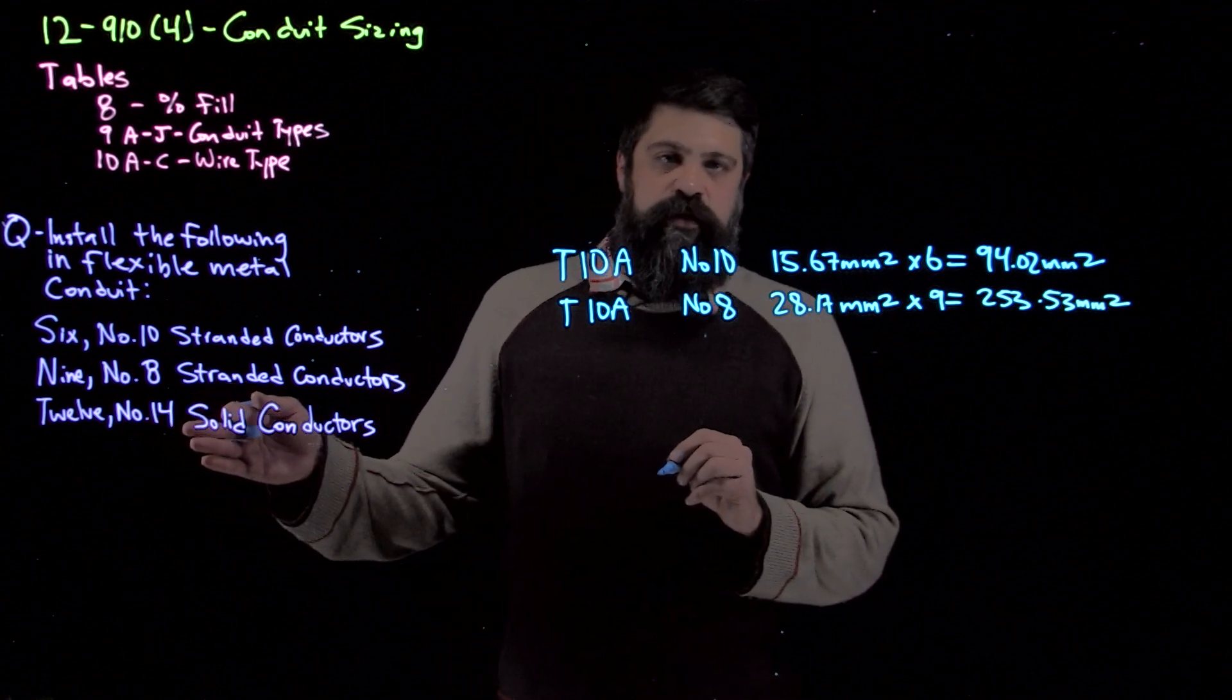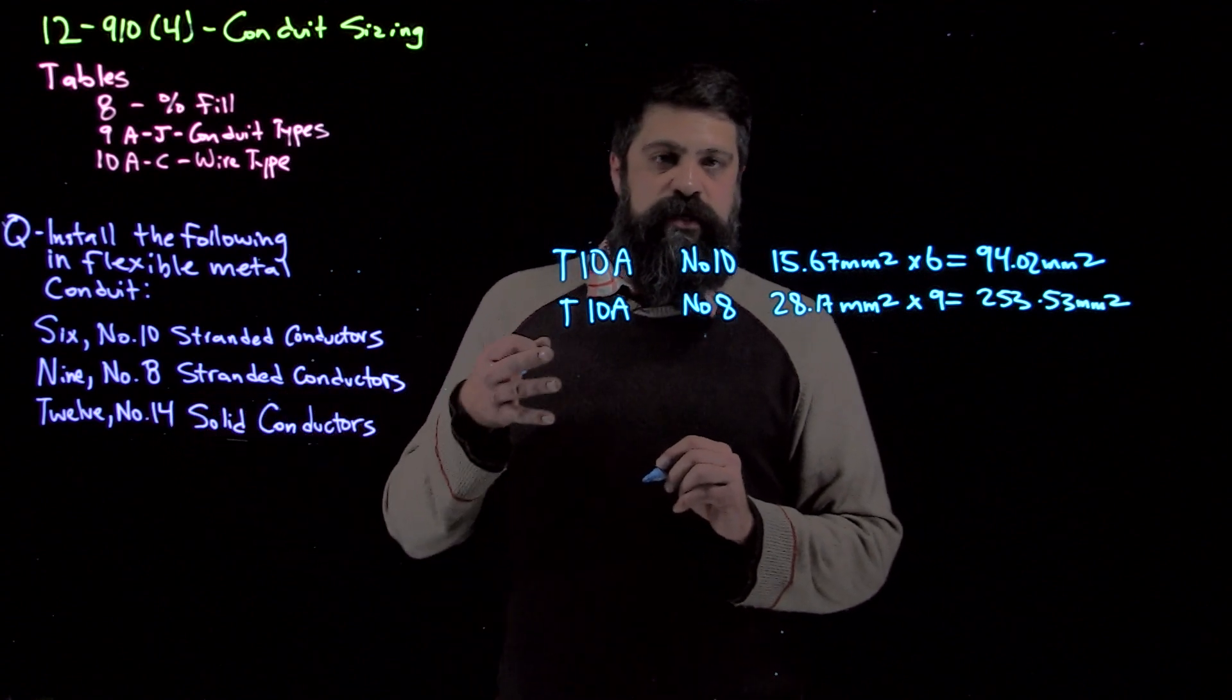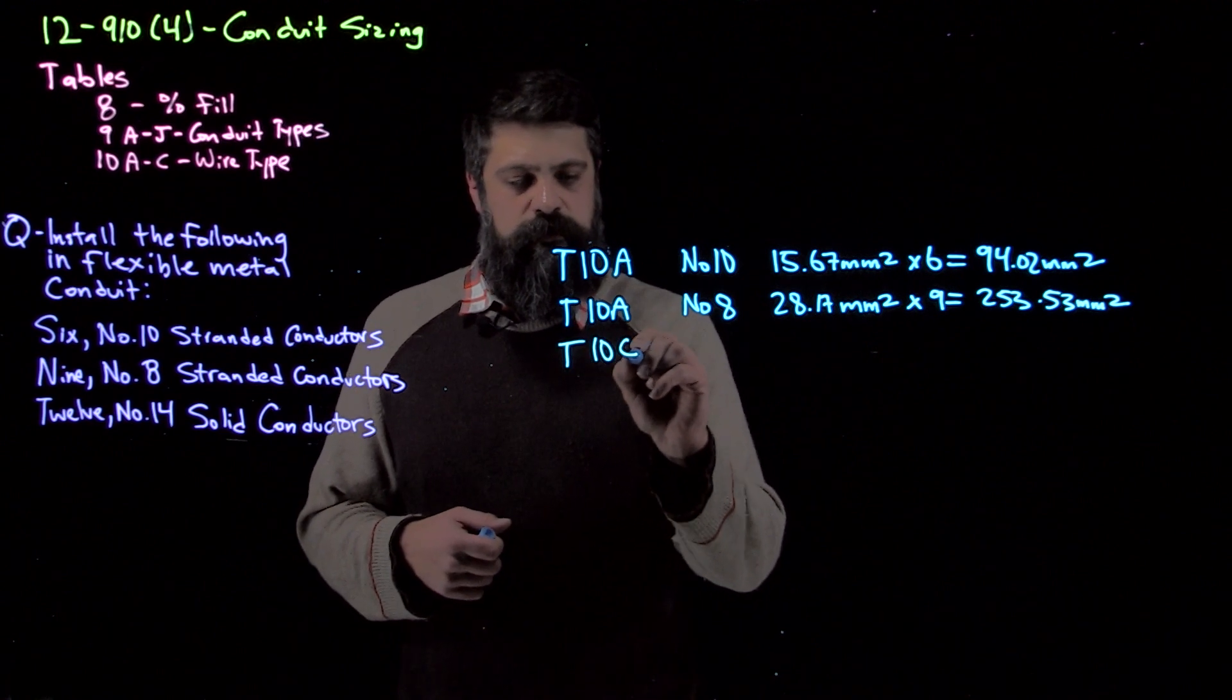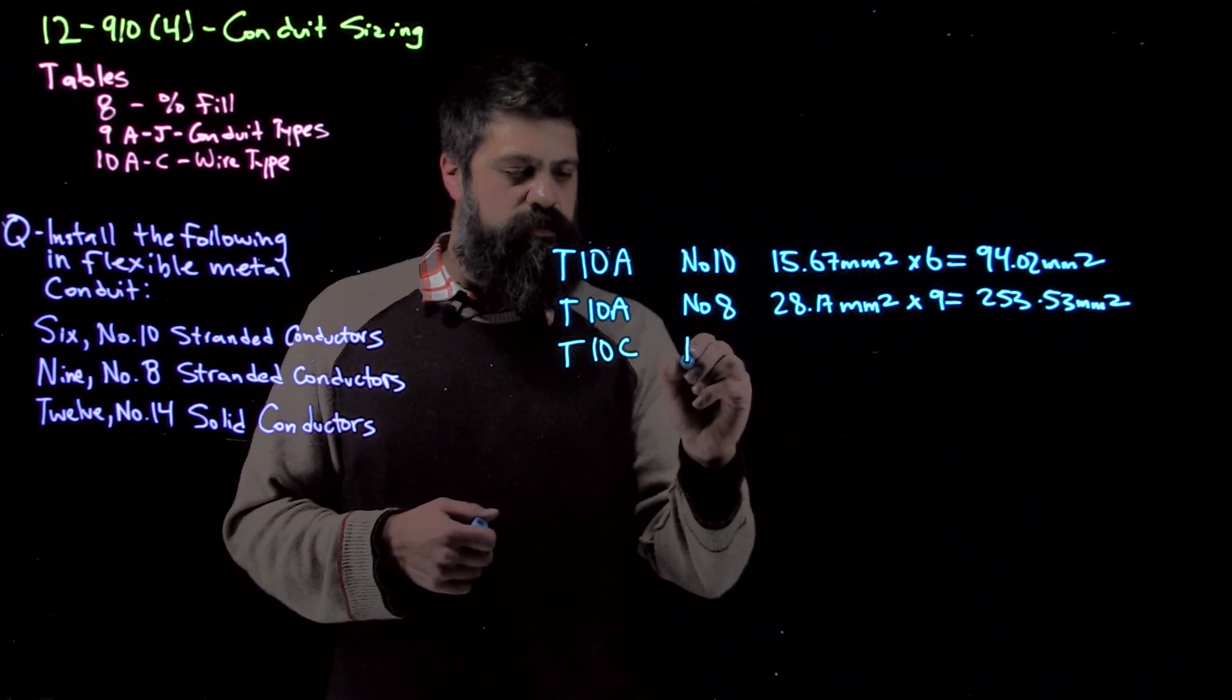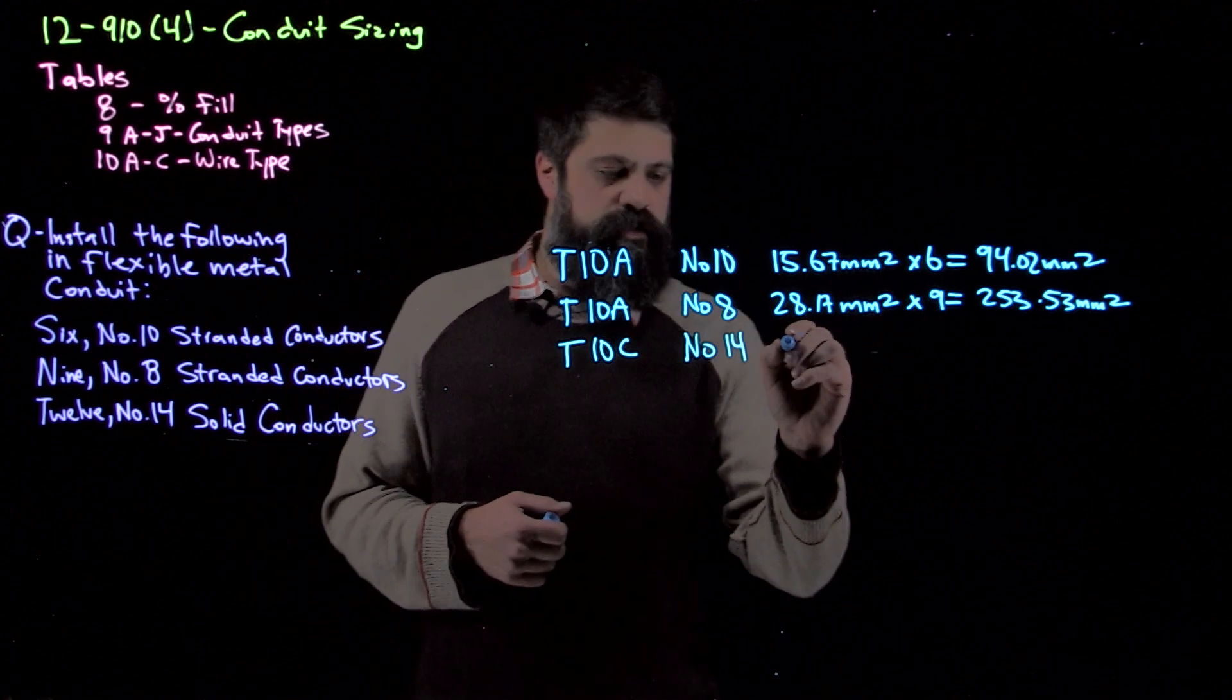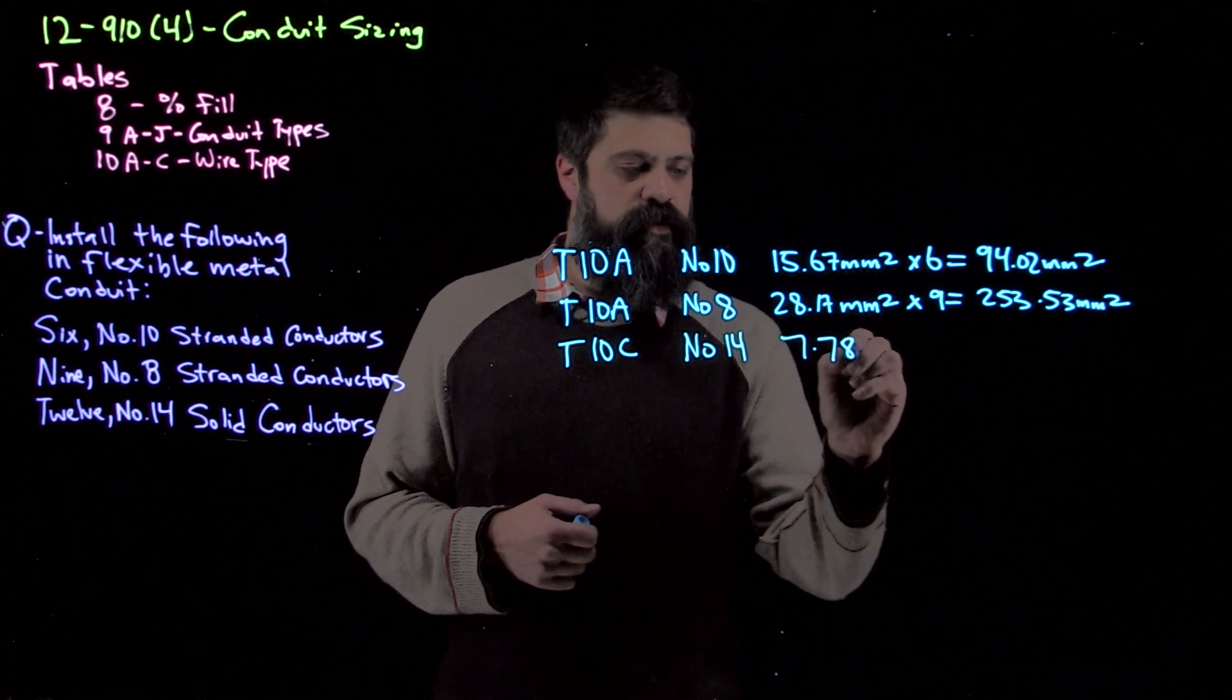The last one we have is a number 14, but this time it's solid, so we're not going to be in 10A. We're going to have to go over to table 10C. So table 10C gives me all of my solid conductors. For number 14, a single one of those is 7.78 mm².